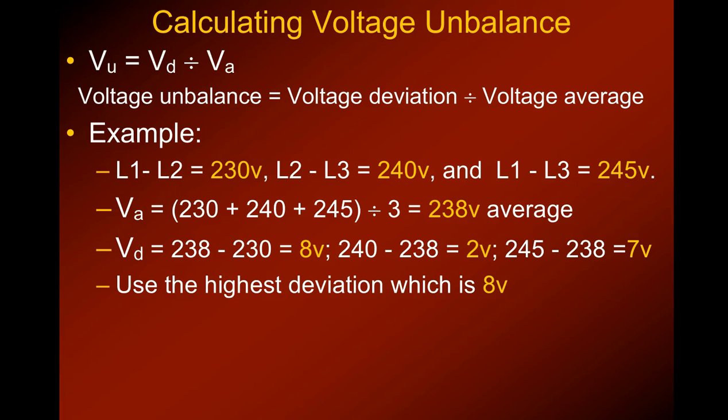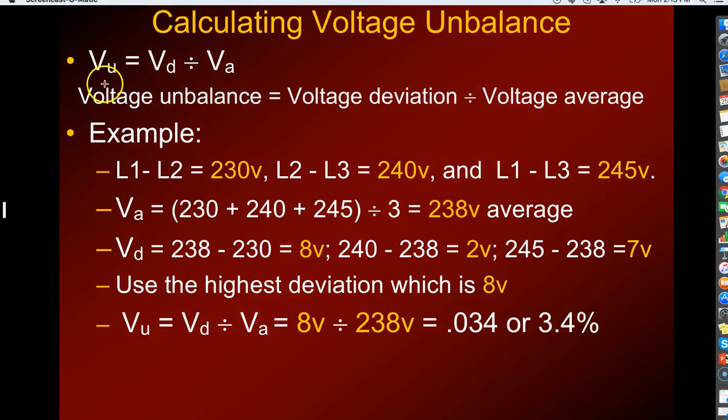And then you're going to use the highest deviation, which in this example is 8 volts. Then you're going to want to apply it to the formula. Now remember, we're solving for the voltage unbalance, which is the VU. We just figured the voltage deviation and the voltage average in these first two formulas. Now we want to come up with the voltage unbalance. So you take the voltage deviation, which was 8 volts, you divide it by the voltage average, which was 238 volts. That comes out to 0.034. And if you remember from school, you have to move that decimal point over two places to get your percentage, and we end up with 3.4% voltage unbalance.